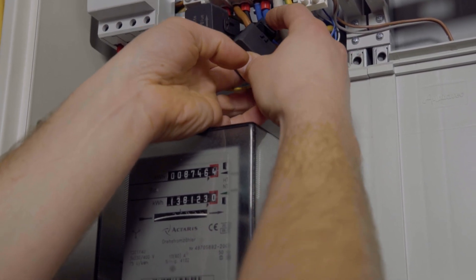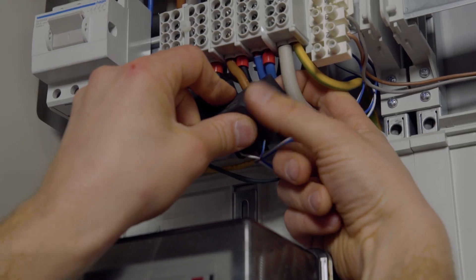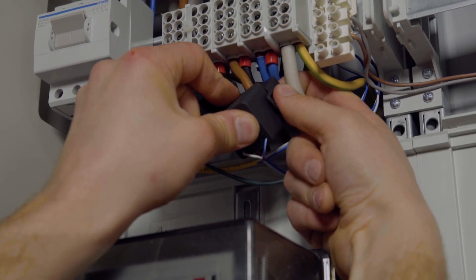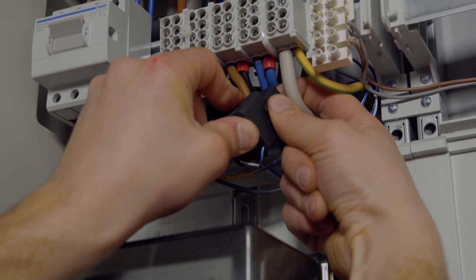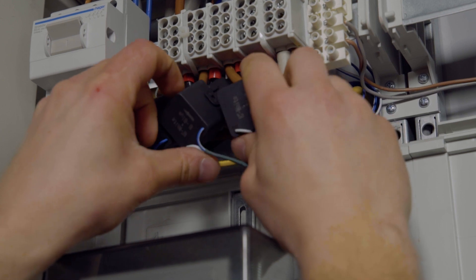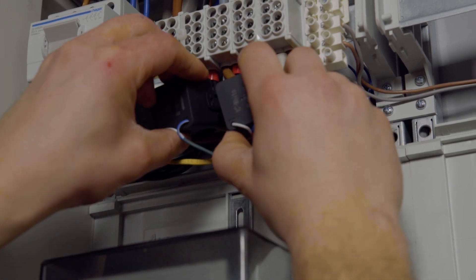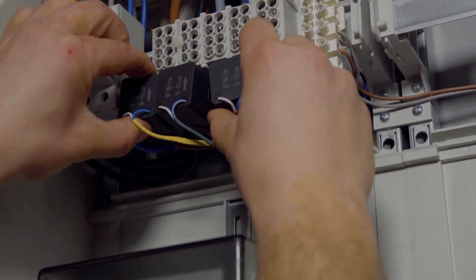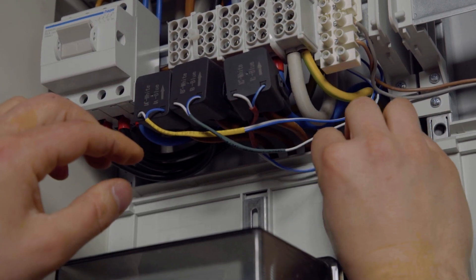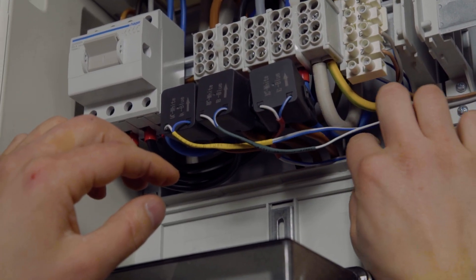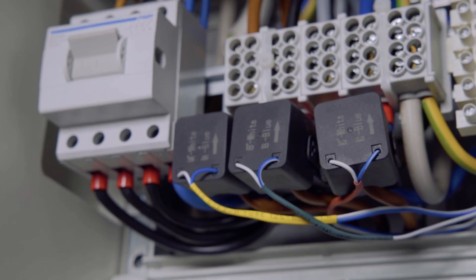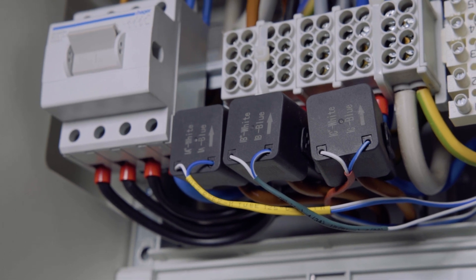If you are installing the first set of CTs, they must be installed directly behind the main household meter at the point where the house is connected to the grid. The whole house must be measured by the CTs. The arrows of the CTs must point into the direction of the house load. That means they should point from grid to house.